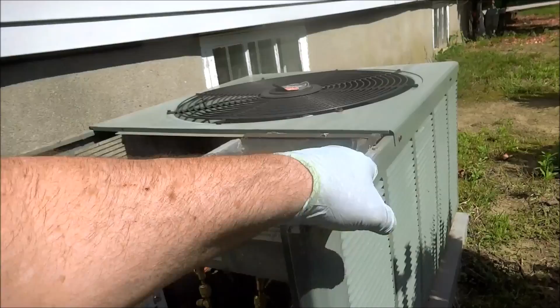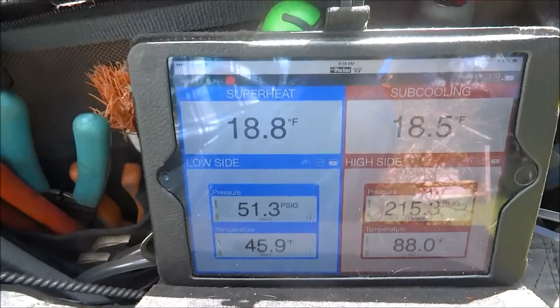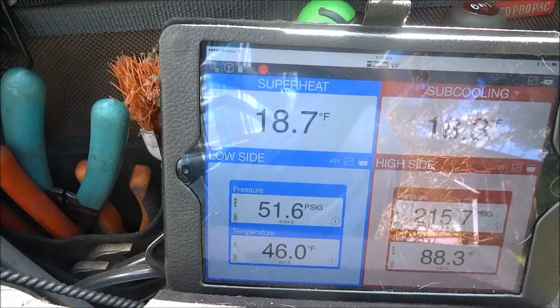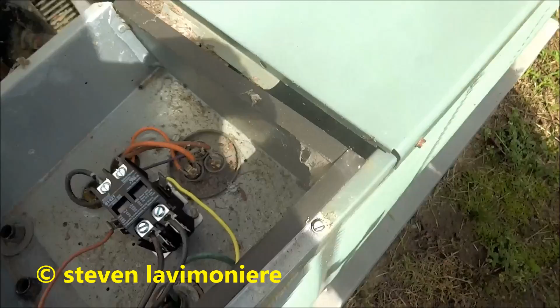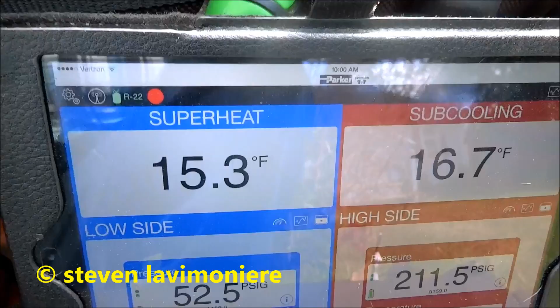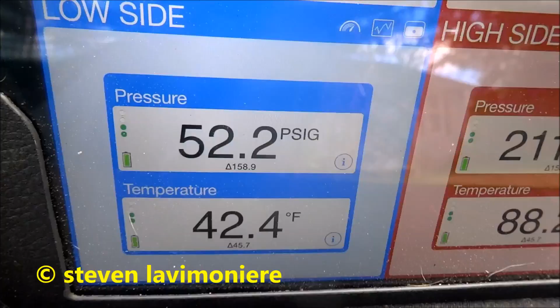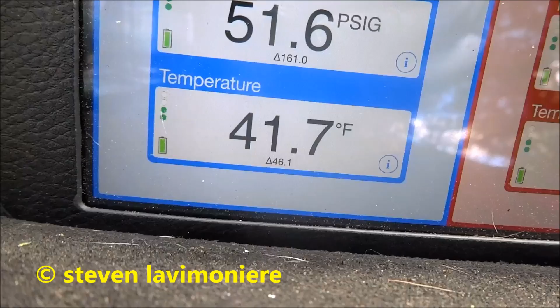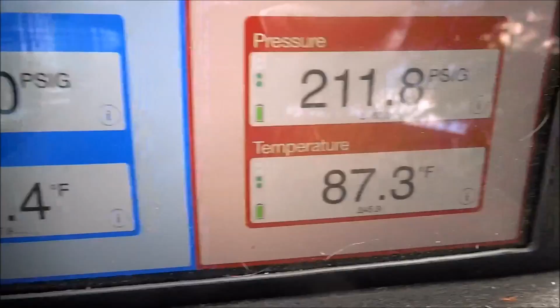If I was going to put a system in this house, I'd probably put a 2.5 ton in here and take this 3.5 ton out. That's all she needs. She's a Rheem classic, y'all. See, they get a lock on that. I should have cut that off, but whatever. Well, I'm going to leave the charge right there. 15 degrees superheat. It's low suction pressure. It is what it is. See the temperature coming back on my line, 41 degrees. That's about the best it's going to get right there.